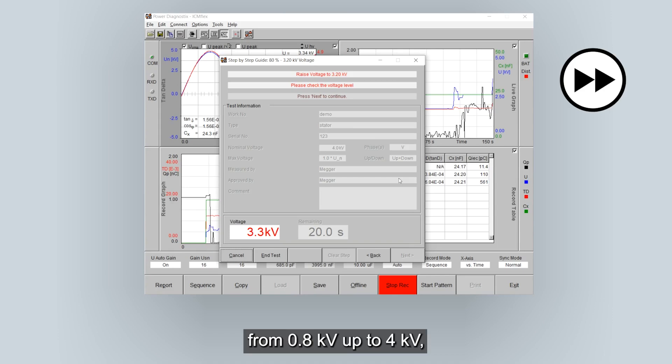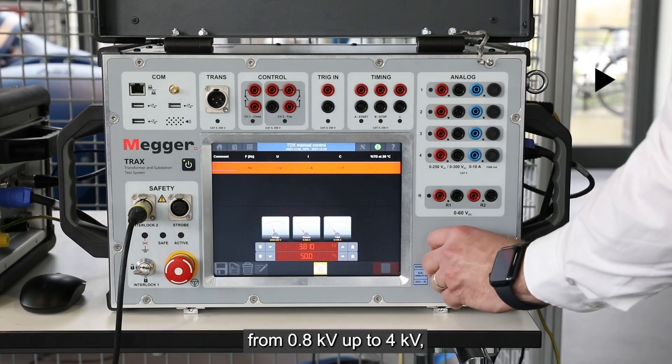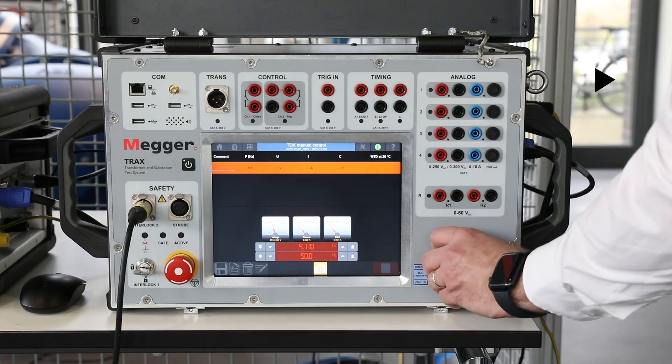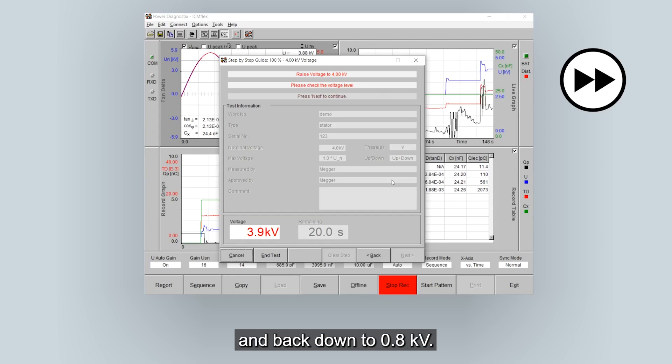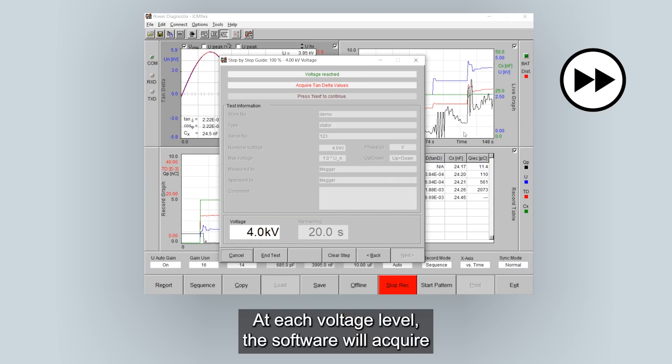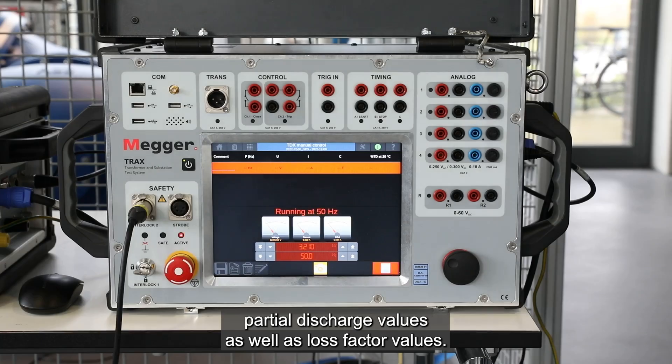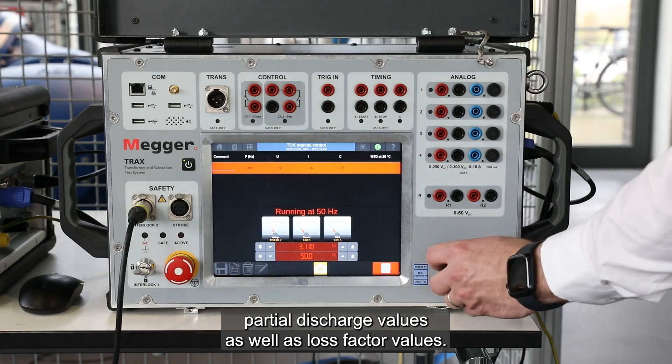The step-by-step guide will guide me through 5 different voltage steps with increments of 800 volts each. From 0.8 kV up to 4 kV and back down to 0.8 kV. At each voltage level, the software will acquire partial discharge values as well as loss factor values.